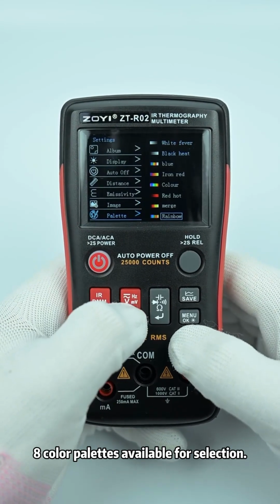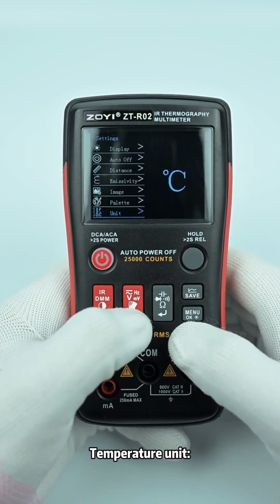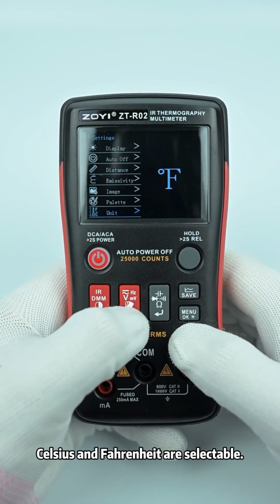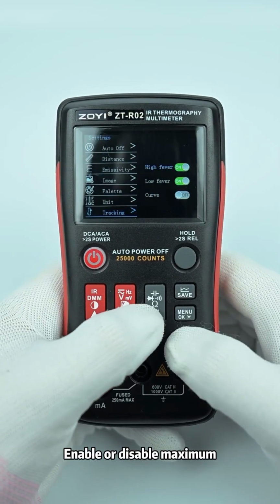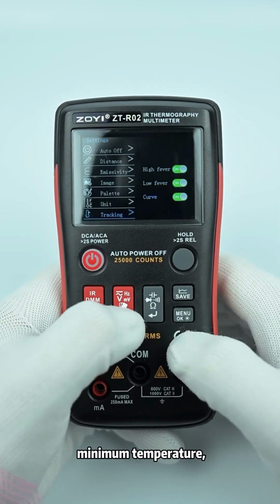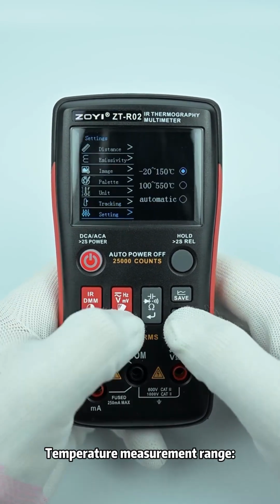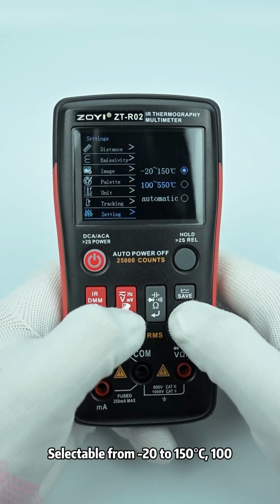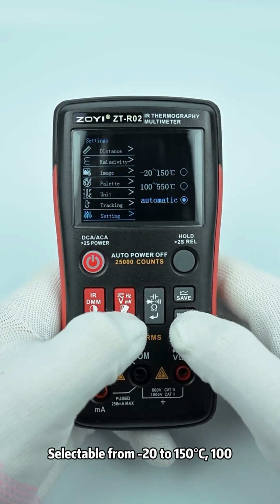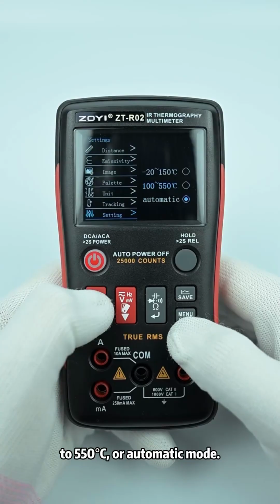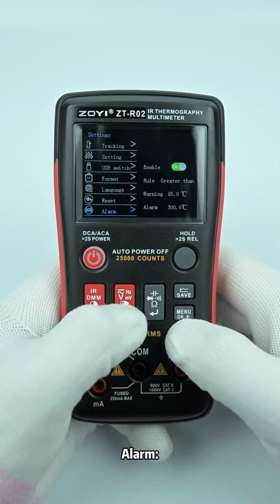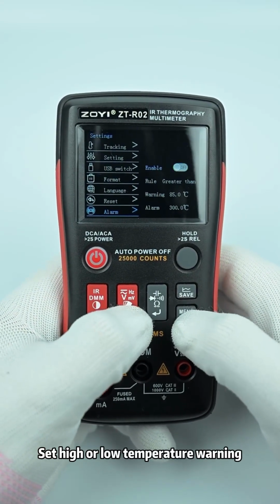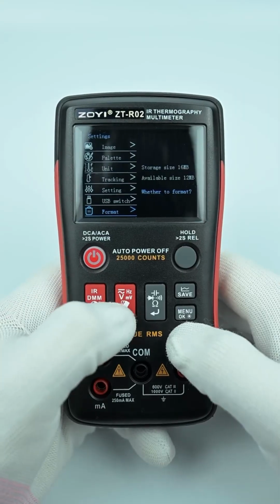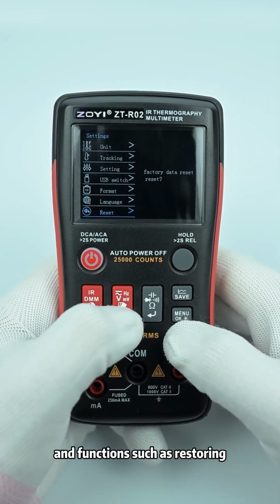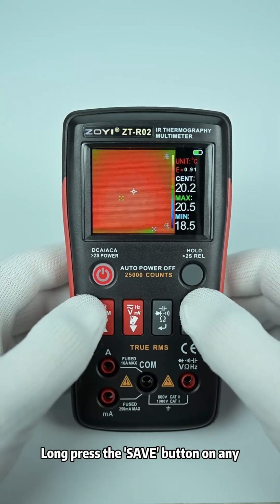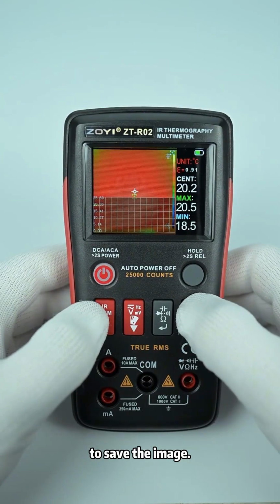Color palette. 8 color palettes available for selection. Temperature unit. Celsius and Fahrenheit are selectable. Temperature tracking. Enable or disable maximum temperature, minimum temperature, and temperature curve. Temperature measurement range. Selectable from -20 to 150 degrees Celsius, 100 to 550 degrees Celsius, or automatic mode. Alarm. Set high or low temperature warning values, as well as formatting, language selection, and functions such as restoring factory settings. Long press the Save button on any screen to save the image.